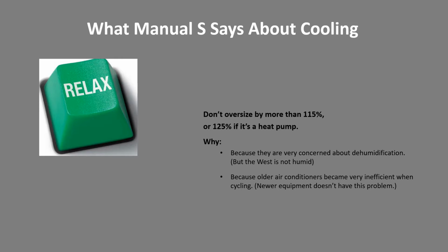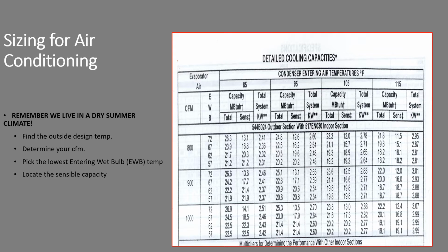Again, just to hit this up: Manual S says don't oversize. Why? Because they are quite concerned about dehumidification. Sizing for air conditioners: every manufacturer presents their detailed capacity just a little bit differently than every other manufacturer, making our lives sort of complicated. But regardless, the process is usually the same.